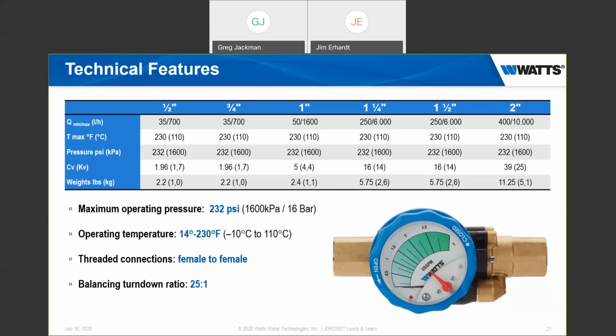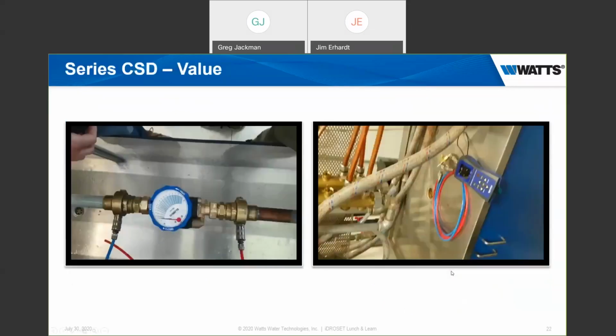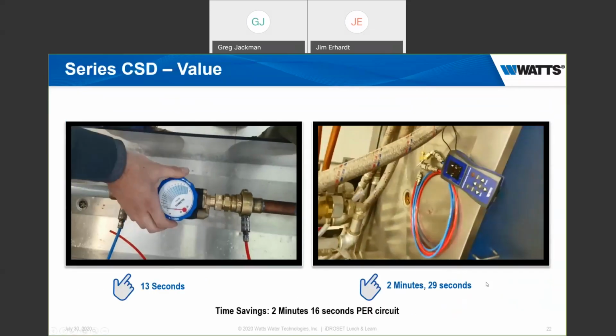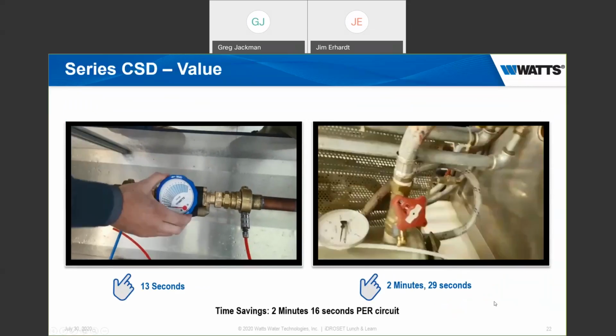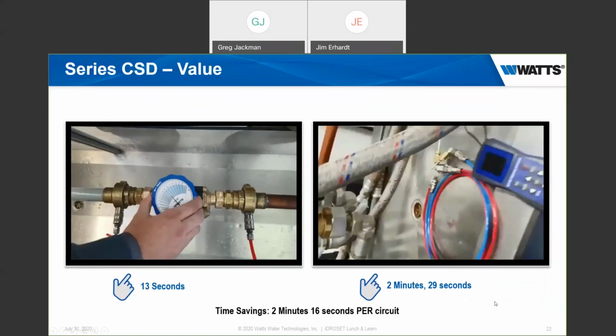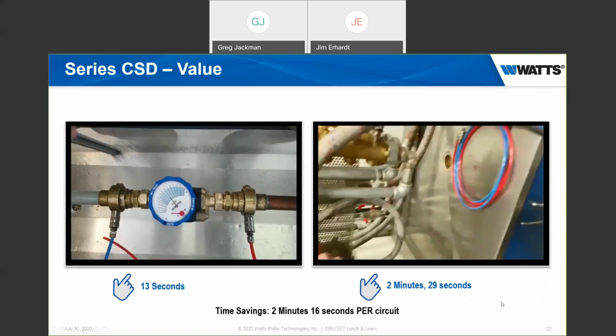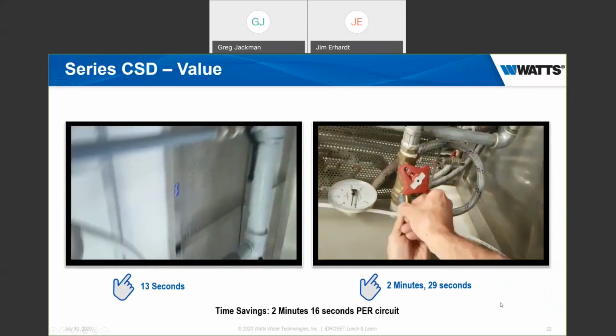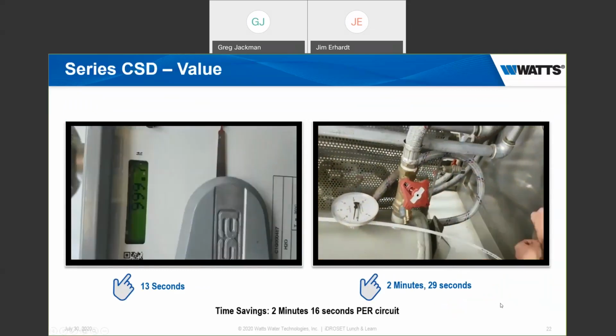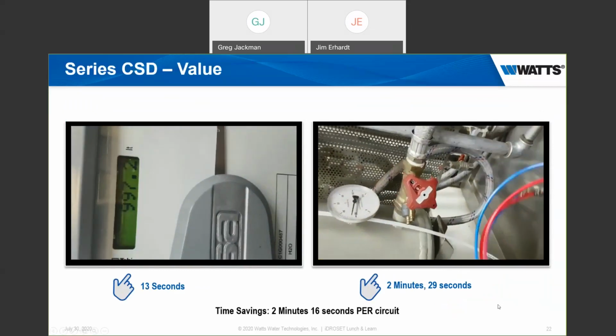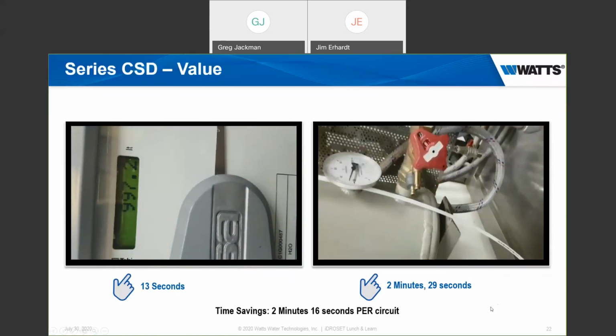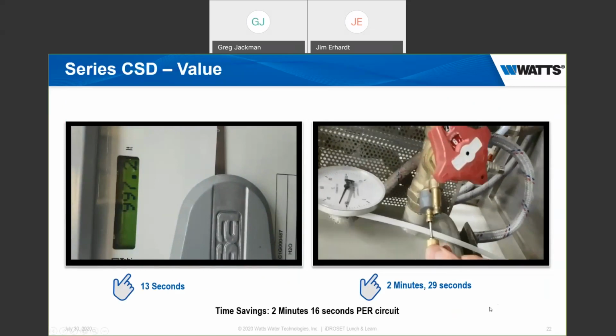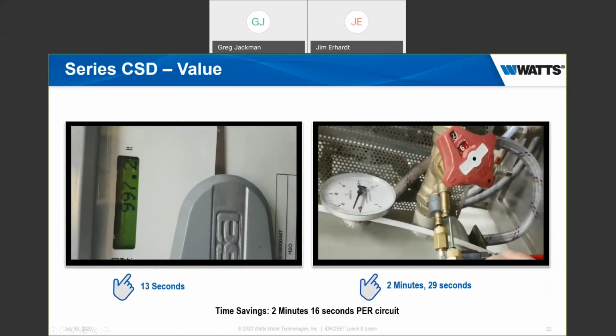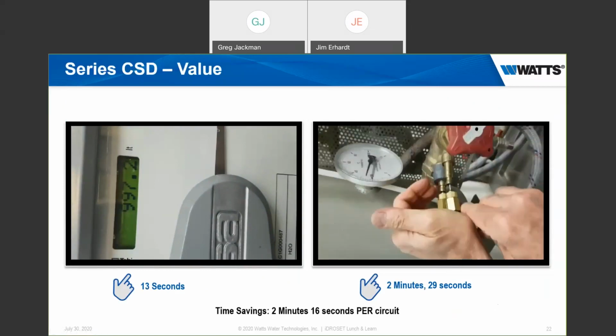And are these available lead-free for use in domestic hot water recirculation? Yes, as per the previous question, we will have those available in Q1 of next year, the lead-free version. It'll be the same valve, except it'll be made with the lead-free alloy, and they will also have unions on each side as opposed to just a standard female pipe thread, and we will have tail pieces available for thread, sweat, and press on the lead-free version.